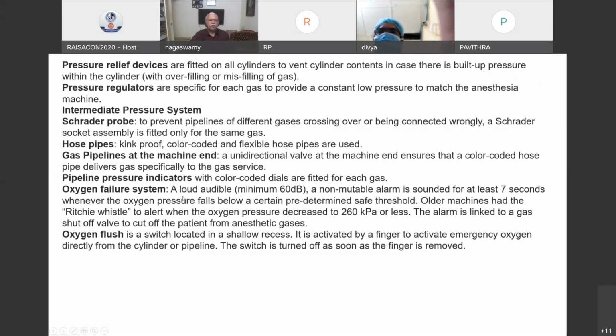Then the oxygen failure alarm, a loud audible alarm which should be a minimum of 60 decibels and it should not be muted. That's a very important thing. Normally any alarm you can silence for a few seconds, but this is not possible here, so that it will sound for at least 7 seconds to capture your attention. So when there is an oxygen failure, it is predetermined to act at a safe threshold. Older machines had what is called the Ritchie whistle. One of the short note questions they may ask you in the Viva is the name of the whistle or the alarm. It's called the Ritchie whistle, to alert when the oxygen pressure decreases to less than 260 kilopascals. It is linked to the gas shutoff valve.